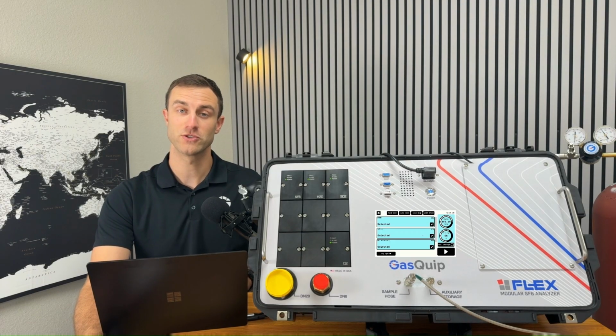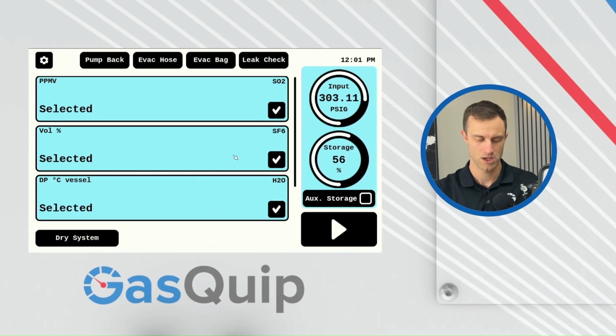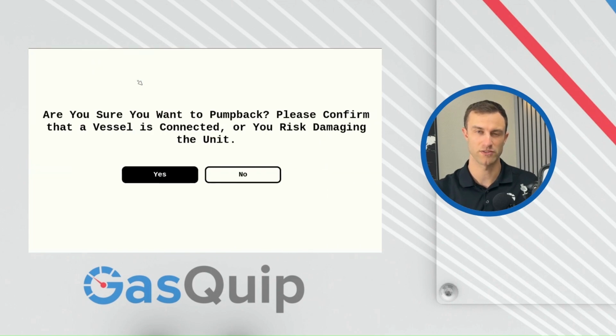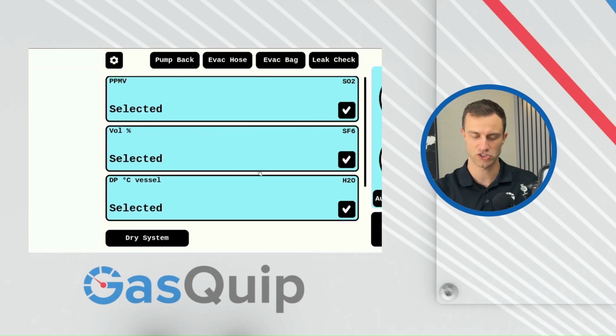Let's talk about some of the special functions that are found on the home screen and when to use them. Up here in the top left, the pump back function takes all of the storage found in the internal of the device, and also if anything's hooked up to auxiliary storage, it'll pump all of that gas back into the gas reservoir that you're testing. So you can use that straight from the home screen or also after a test is finished.